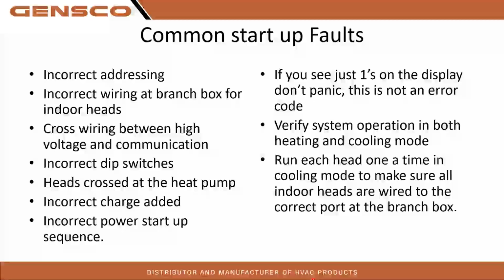Common startup faults. So this is just a quick list of some of the stuff that we see pretty frequently on the tech line for guys calling in for new systems. Incorrect addressing, incorrect wiring, crosswire between high voltage and the communication blowing up boards. We discussed that. Incorrect dip switch settings. Heads crossed. I put heat pump. I need to fix that. Heads crossed at the branch box.